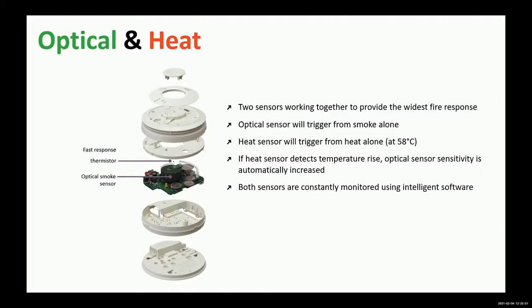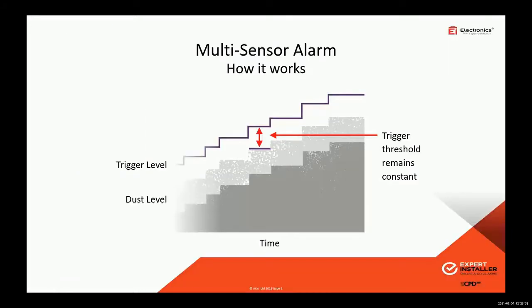But there's intelligence built into the unit as well, and this is what makes it probably the best unit on the market. If the heat sensor detects a rise in temperature, then the optical sensor becomes more sensitive. As I said earlier, when we were speaking about the thresholds we have to manufacture the optical unit at, it's between 2 and 4%, and we automatically have it in the middle of that, at 3% as the threshold for the obscuration level. But if this unit sees a rise in temperature, that automatically drops from 3% down to 2%, which makes it a lot more sensitive. So we get the information about a fire situation a lot faster than we normally would. That's another advantage of this unit.